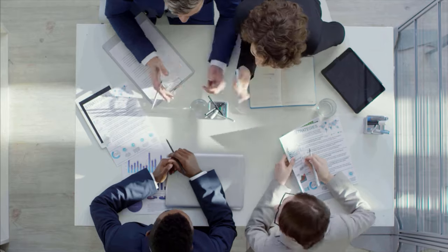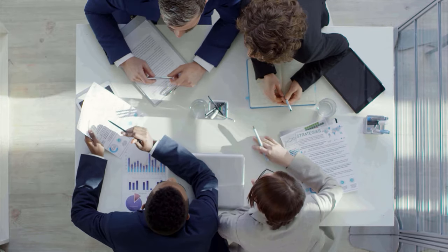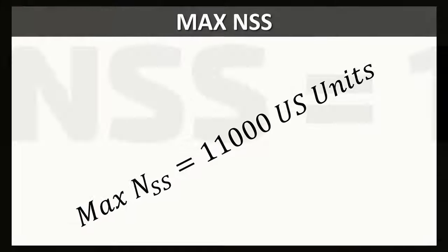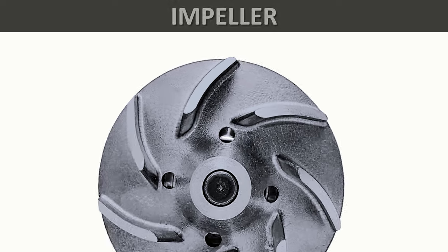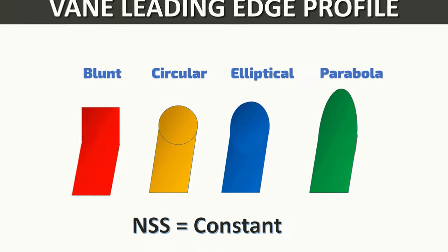Tip number four: talk to pump manufacturers and get the best pump design to meet your lower inlet pressure requirements. Suction performance and operating window used to be inversely proportional to each other. Suction specific speed — an indicator of impeller design — greatly affects suction performance. Increasing this value yielded less inlet pressure requirements at BEP but came at the cost of a reduced operating window, hence 11,000 US units used to be the upper limit for suction specific speed. However, for the past few decades, computational fluid dynamics and other design improvements have provided tools for pump engineers to design pumps with the best possible suction performance without compromising the operating window.